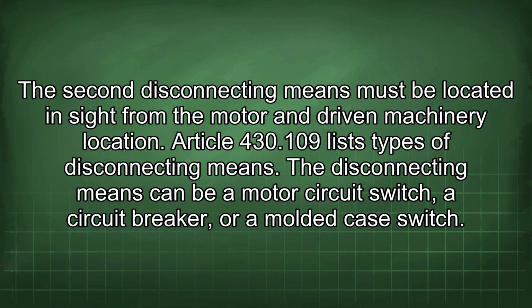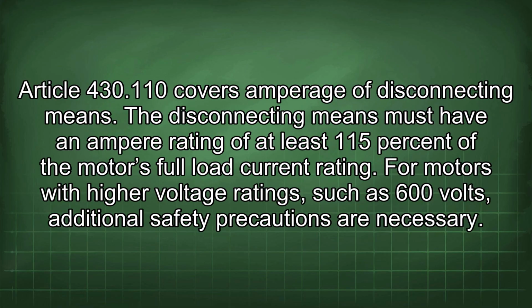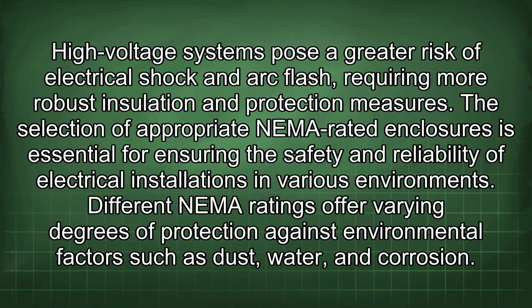Article 430.109 lists types of disconnecting means. The disconnecting means can be a motor circuit switch, a circuit breaker, or a molded case switch. Article 430.110 covers amperage of disconnecting means. The disconnecting means must have an ampere rating of at least 115% of the motor's full load current rating. For motors with higher voltage ratings, such as 600 volts, additional safety precautions are necessary. High voltage systems pose a greater risk of electrical shock and arc flash, requiring more robust insulation and protection measures.